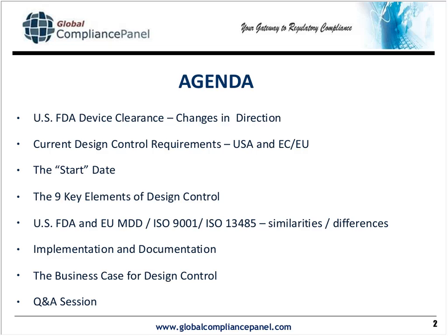Type in QSIT and pull it up and keep it, because it explains not only the key audit areas, but the flow chart that the FDA uses in going through those key areas and how one can feed into the other, like CAPA can feed into production and process controls, etc. But again, the key point is that design control since 1996-97 has become a key area for FDA audit.